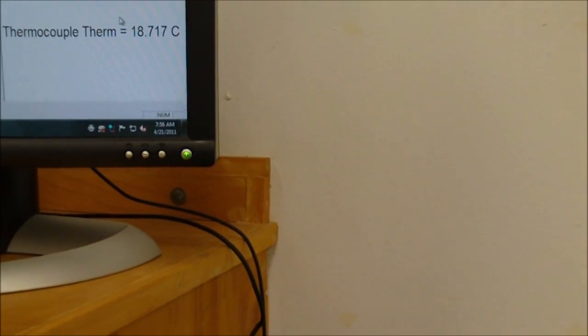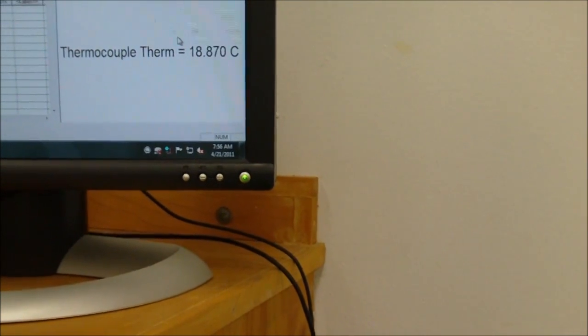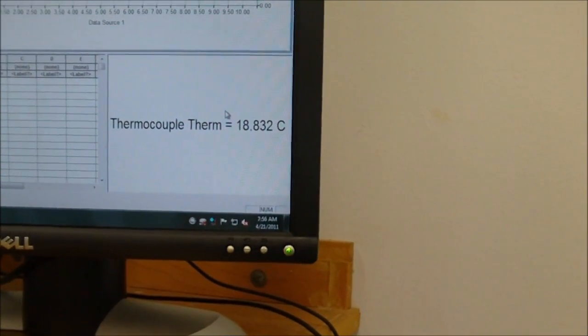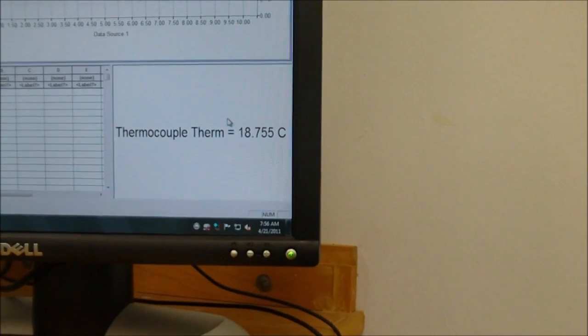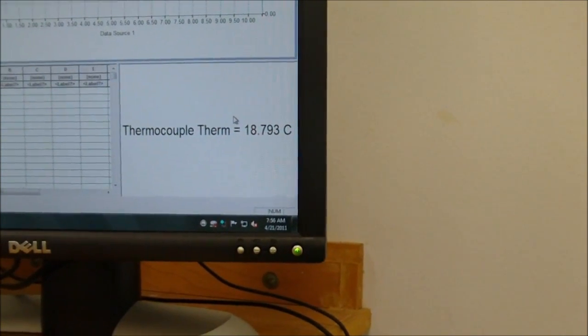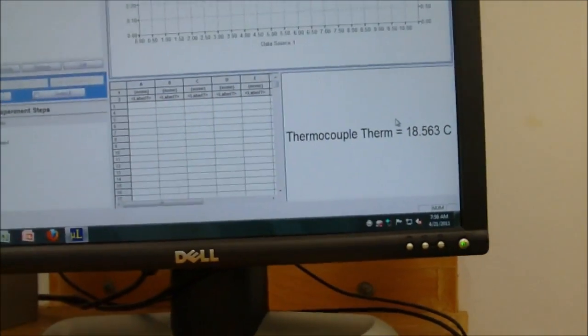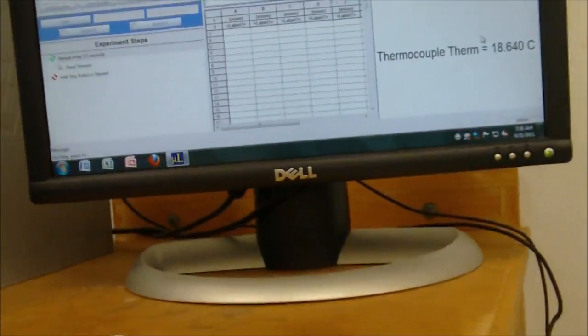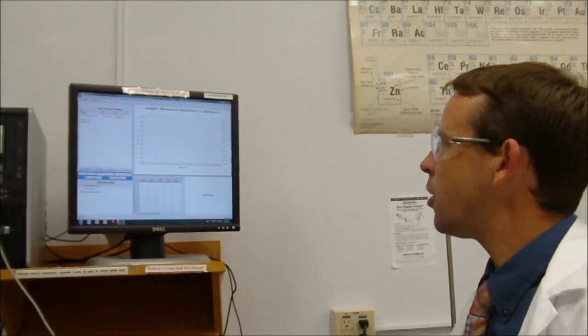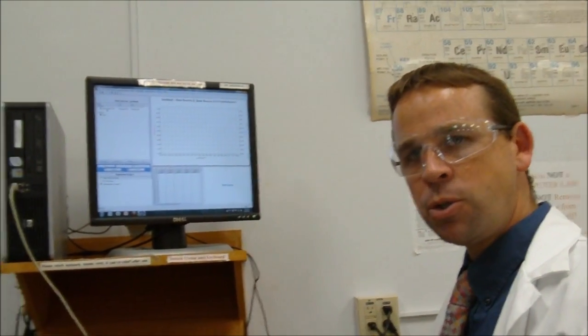So if for some reason this value goes to some unreasonable temperature like 1,000 or 0.000005 or something like that, then we know that it's not working. But here we have it back at room temperature and it's about 18 degrees Celsius. All right, so we've calibrated our thermocouple that way. So now I have a thermocouple, a temperature sensor.